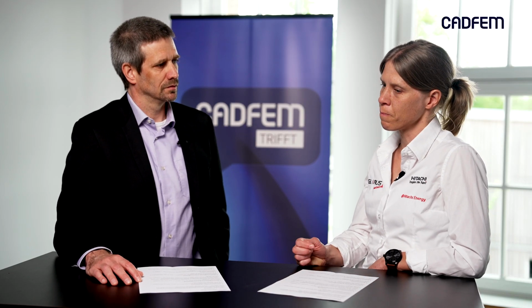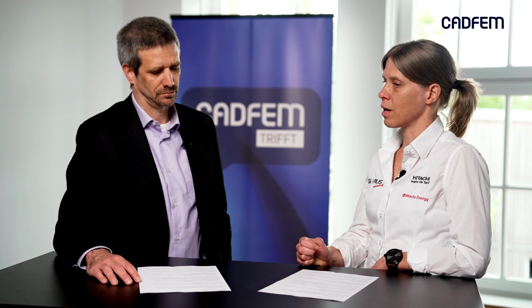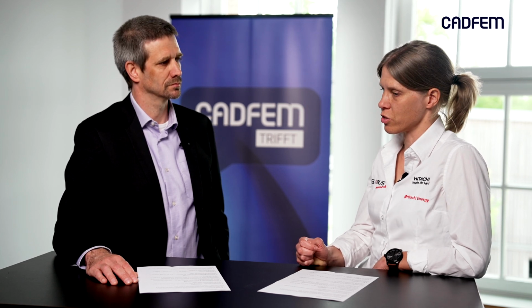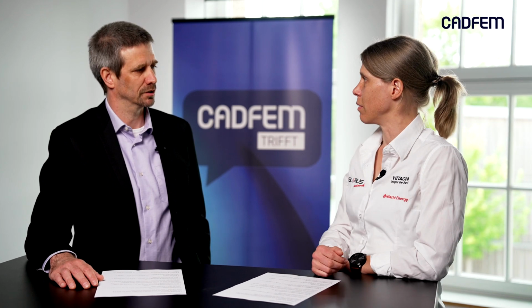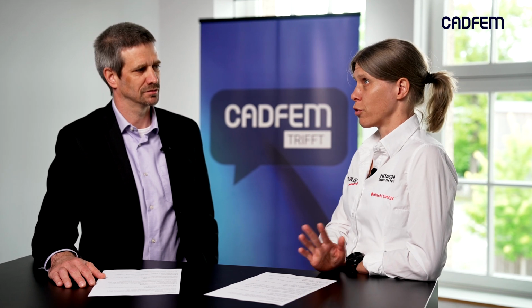But then we also have to consider the structural integrity of the transformers. This is very important, and in this case we do electromagnetic simulation with Maxwell and couple it with structural simulation to see if the transformer, for example, withstands short circuit forces. So this is one example. Another example could be NVH, or noise, vibration and harshness. This is also important, especially for distribution transformers, because they tend to be placed near where people live. They have to be relatively silent. So these are a few examples.